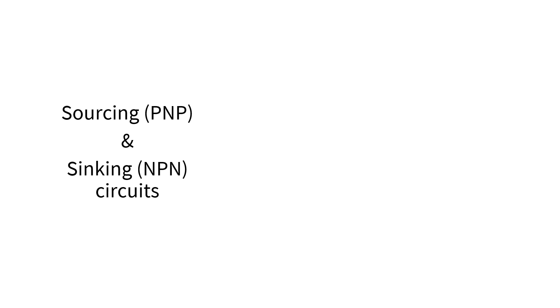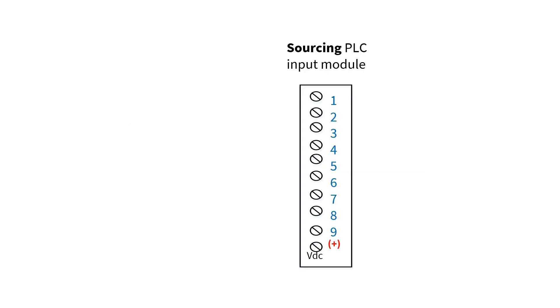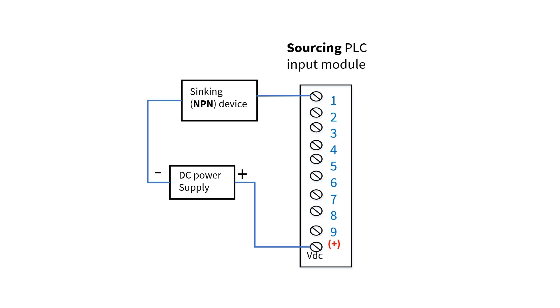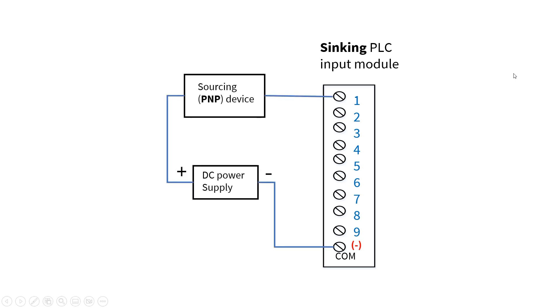A sourcing and sinking circuit consists of the following parts: sourcing part, sinking part, and a power supply. Here I want to show you in general how the sinking and sourcing circuit diagrams look. Here I have a sourcing PLC input module connected to a sinking NPN device, then to a power supply, which is connected back to the sourcing PLC input module. For the other configuration, I have a sinking PLC input module connected to a sourcing PNP device that is connected to the positive side of the power supply, which is also connected back to the sinking PLC input module.